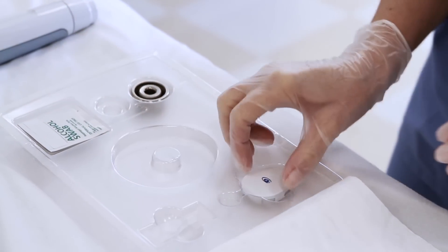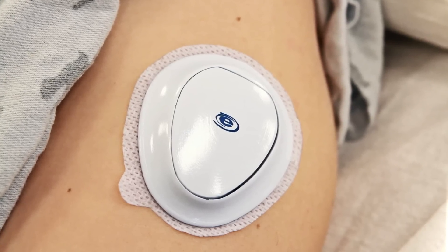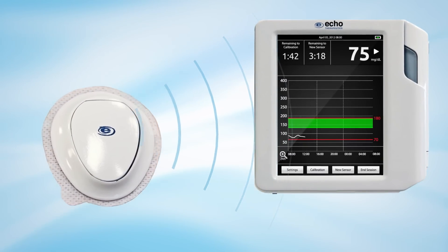The glucose sensor is applied to the site prepared by Prelude. After an initial warm-up period, the patient's current blood glucose level is used to calibrate the system. The Symphony glucose sensor then measures glucose levels and wirelessly transmits them every minute to a remote monitor.